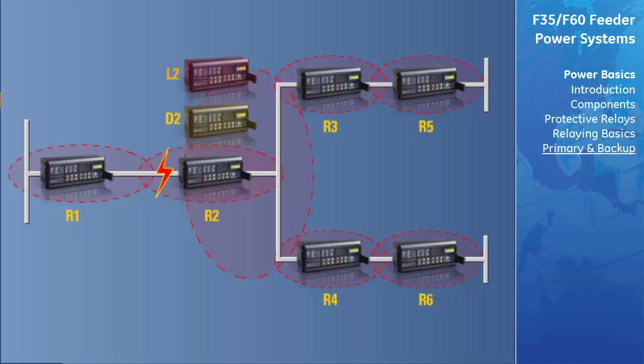When a fault occurs at location F, relays R1 and R2 are the primary relays programmed to identify and clear the fault. Assuming R2 fails to operate, duplicate relay D2 should have operated at the same time. If D2 has also failed, the local backup relay L2 should now operate a short time after the primary and duplicate relays due to its coordination with them. If all three fail, relays R3 through R6 provide remote backup to R2, D2, and L2.